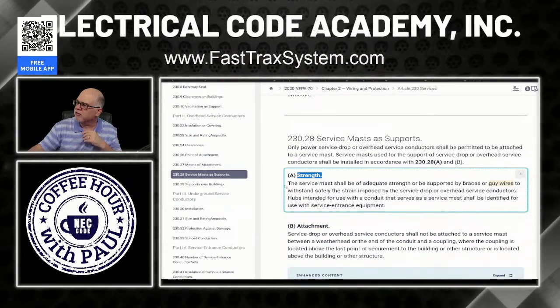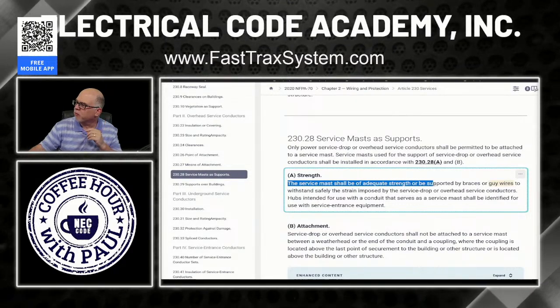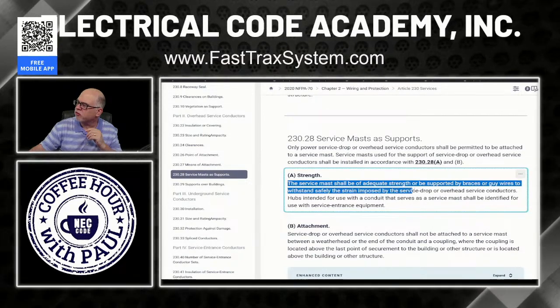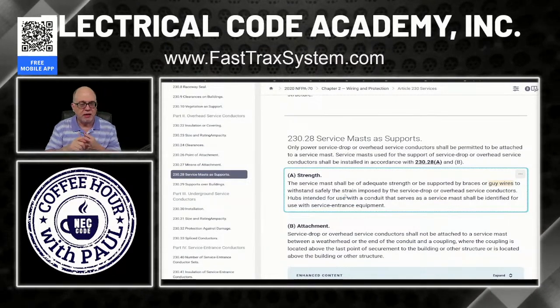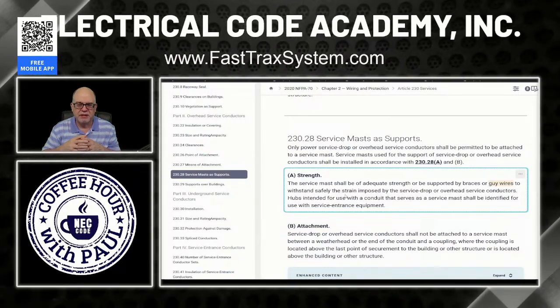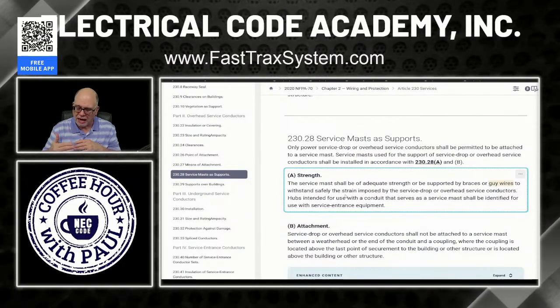So here we are over in the code. It says the service mast shall be of adequate strength or be supported by braces and guy wires to withstand safely the strains imposed by the service drop or overhead service conductors. Hubs intended for use with conduit that serve as a service mast shall be identified for use with service-entrance equipment. Now, talk about the strain. It says adequate strength. Who determines what's adequate strength? Well, a lot of times the utility companies will tell you what they expect you to use. They'll say whether you're supposed to use rigid or IMC.